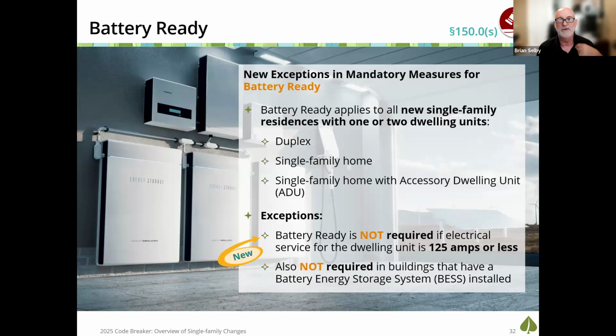This requires that the provisions for the future installation of that battery are installed. This means that some of the circuits are installed. There need to be 4 circuits that run through a sub panel. There are requirements that reserve space next to the service panel, as well as any interconnections and wiring be made. Now, the new exception outside of that code requirement says that if the service panel for that dwelling is rated for 125 amps or less, then battery ready is not required.